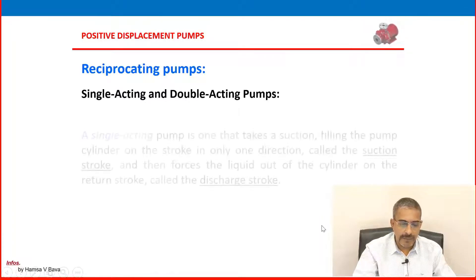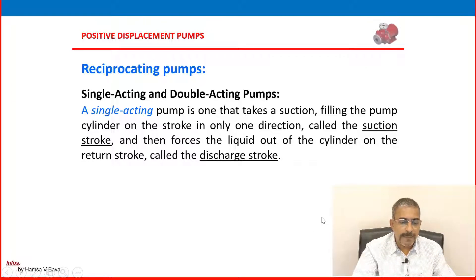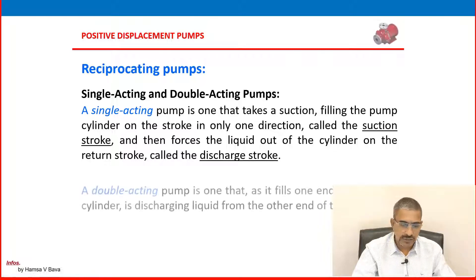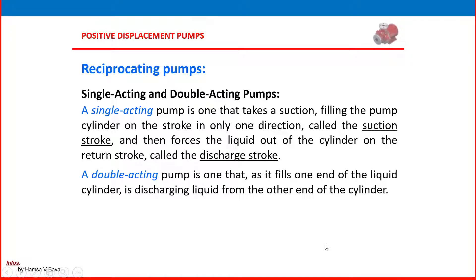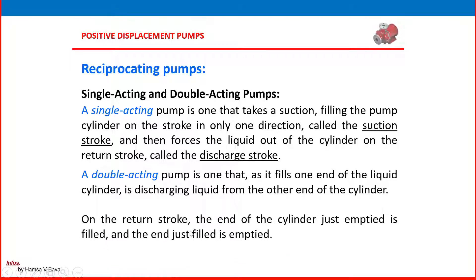For single acting and double acting pumps: a single acting pump takes suction, filling the pump cylinder on a stroke in only one direction called the suction stroke, then forces the liquid out on the return stroke called the discharge stroke. A single acting pump has only one suction and one discharge. A double acting pump fills one end of the liquid cylinder while discharging liquid from the other end. On the return stroke, the end just emptied is filled and the end just filled is emptied.